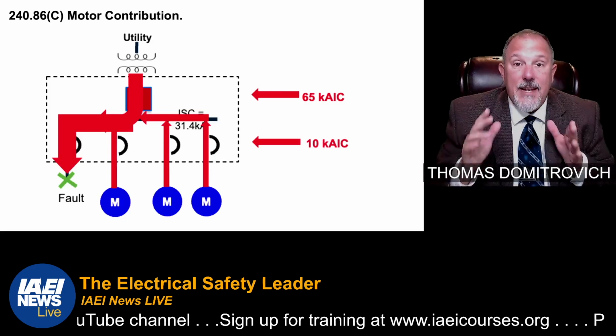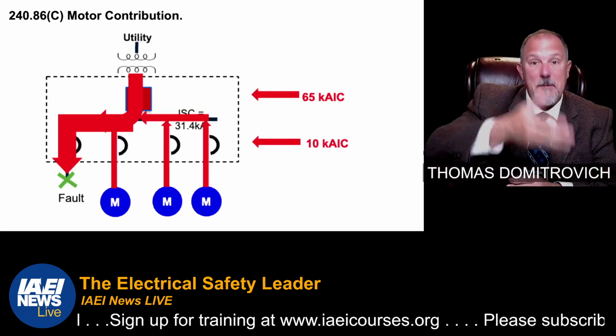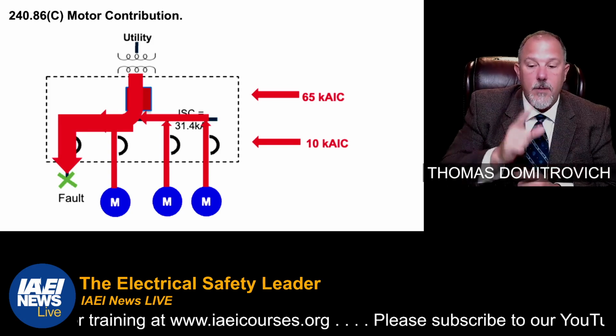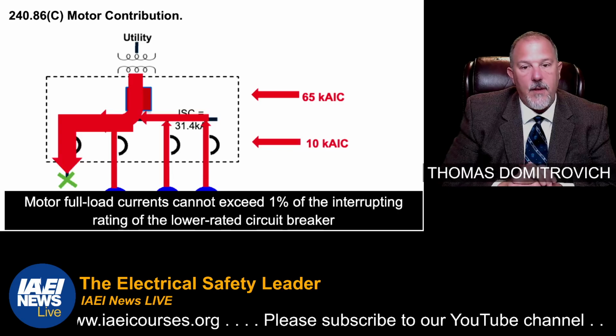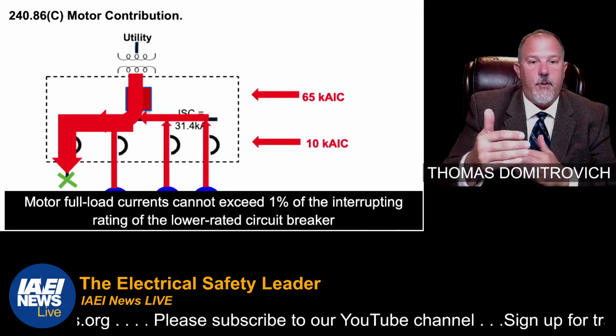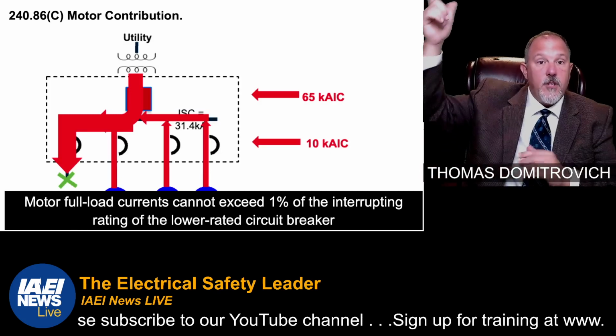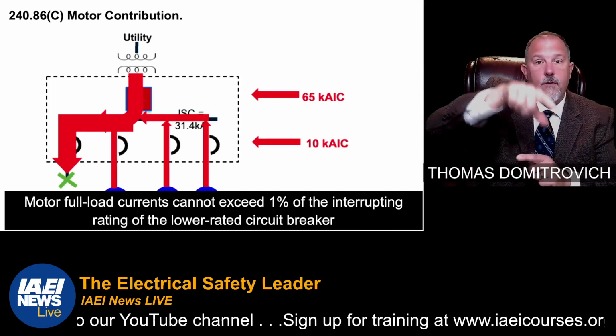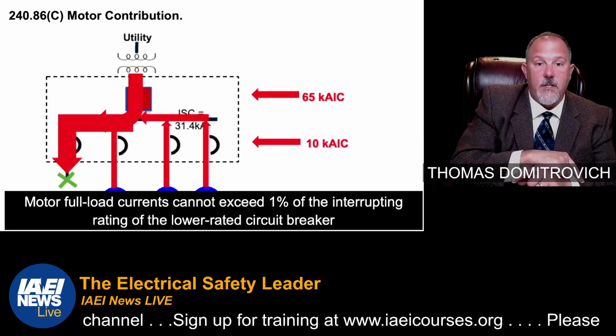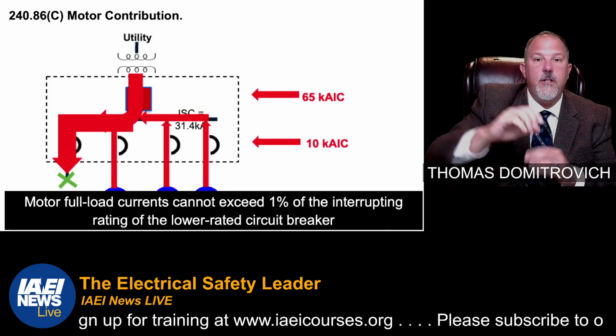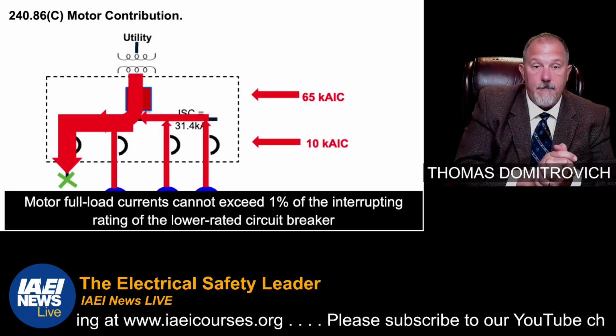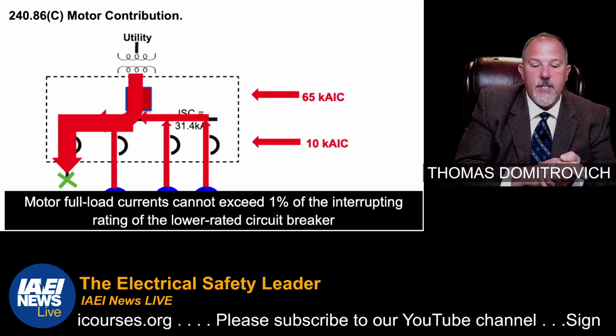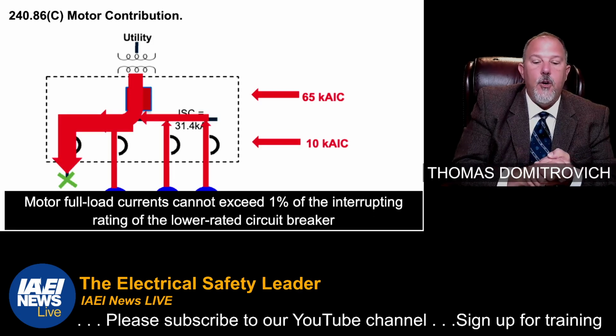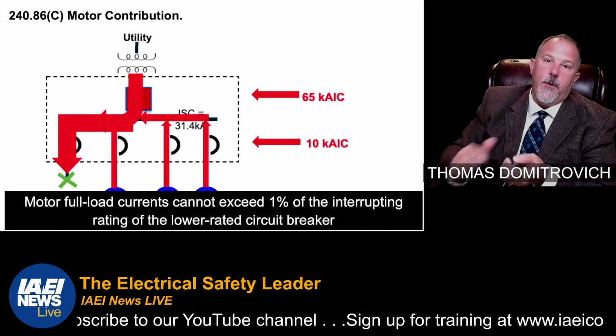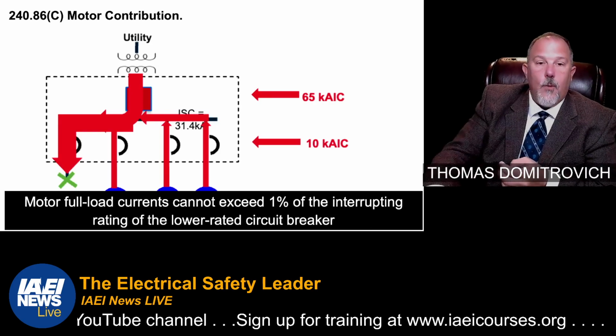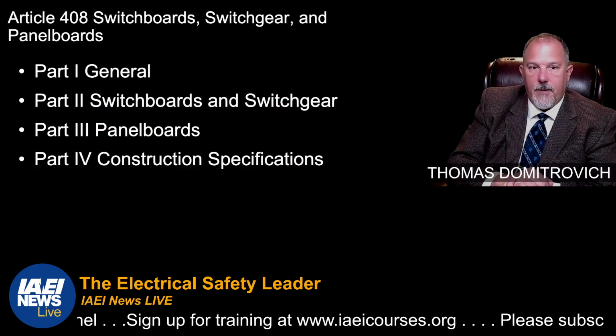These devices have never been tested that way, ever. They are always tested with the same amount of fault current passing through both of them. So what the code does is it limits the amount of fault current that you can contribute from downstream motors, not upstream. Because if it was upstream of that main overcurrent device, then all of that current would be flowing through both devices. Only when the motor contribution is in between the two devices, like what you see here, can I not exceed 1% of the interrupting rating of the lower rated circuit breaker. So I add up all the full load amps, and I can't exceed 1% of the lower device interrupting rating.